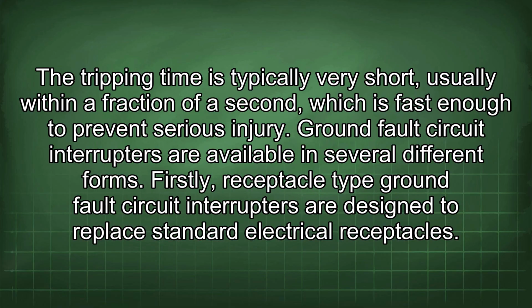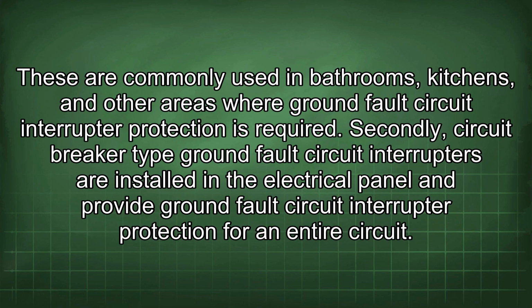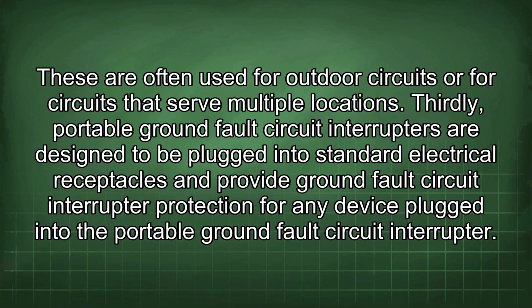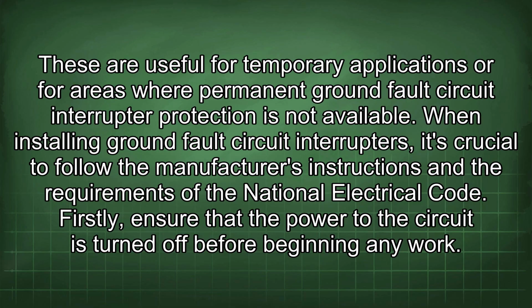Firstly, receptacle-type ground fault circuit interrupters are designed to replace standard electrical receptacles. These are commonly used in bathrooms, kitchens, and other areas where ground fault circuit interrupter protection is required. Secondly, circuit breaker-type ground fault circuit interrupters are installed in the electrical panel and provide protection for an entire circuit. These are often used for outdoor circuits or for circuits that serve multiple locations. Thirdly, portable ground fault circuit interrupters are designed to be plugged into standard electrical receptacles and provide protection for any device plugged into the portable unit. These are useful for temporary applications or for areas where permanent protection is not available.